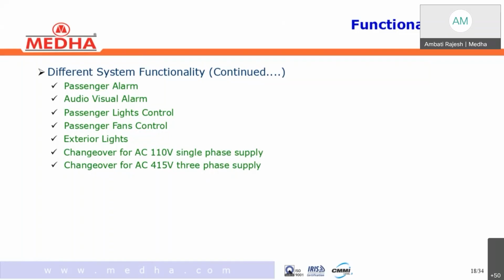In general, if we detach the train, all the EOL loops, EBL loops, BAL loops will get open. Cab occupied loop, everything. But intentionally, we wish to move now only 1 basic unit. So at that time, if we select that single unit operation, the system ignores those loops and with limited speed, it allows the traction. That is for shunting purposes.